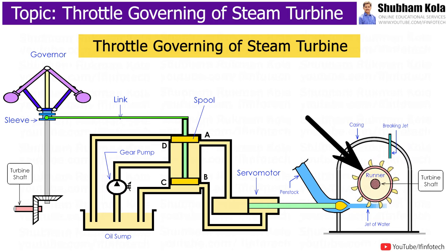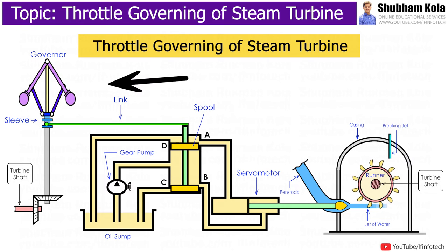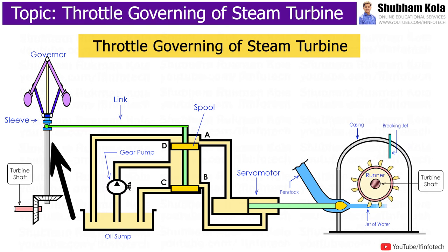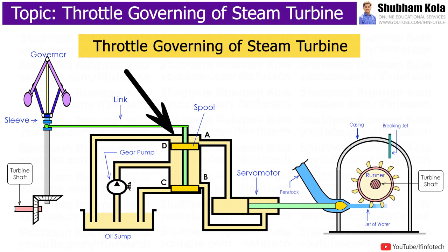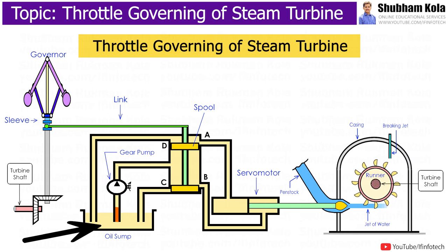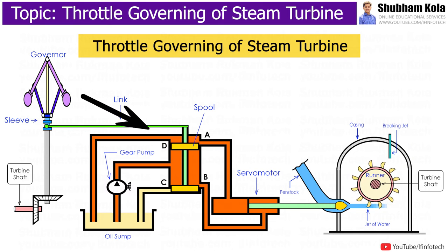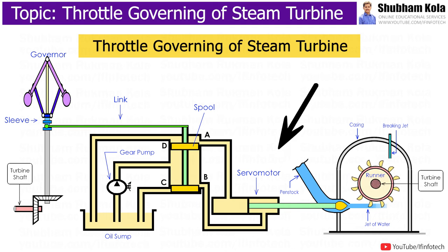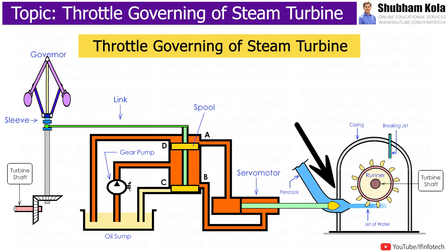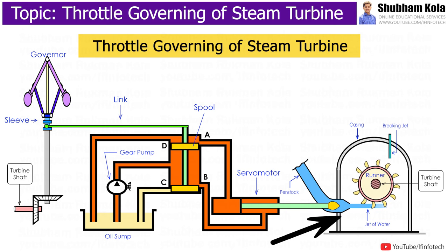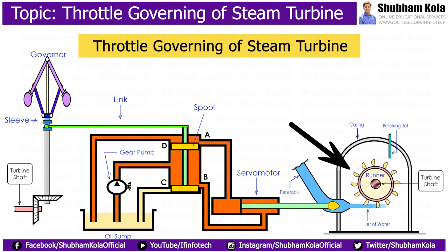Now suppose the load on the generator is suddenly increased — this leads to a reduction in rotational speed of the turbine and governor. Due to this, the governor balls come inward and the sleeve goes down, pushing the spool in the downward direction. Hence, oil under pressure flows through pipe B to the bottom side of the servo motor, while ports A and D are free for oil return. Oil enters inside the cylinder and pushes the piston, operating the throttle valve to increase its opening, allowing more steam to pass through the turbine, which hikes the speed of the turbine again.